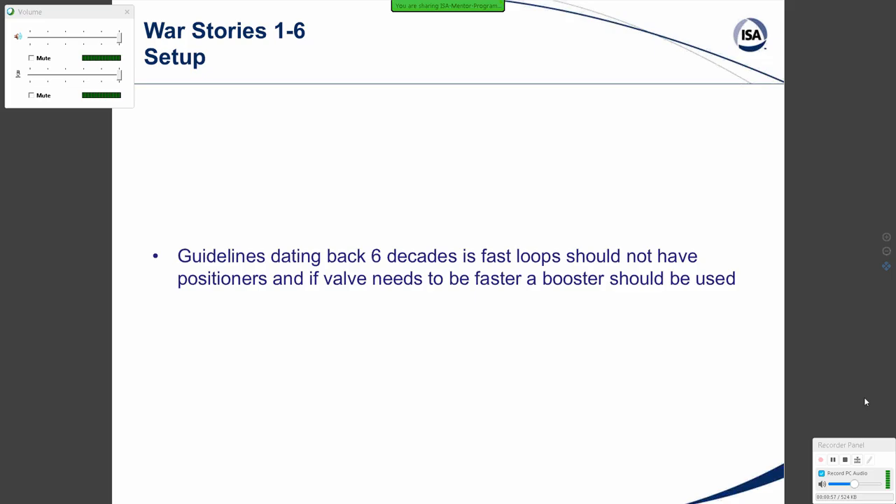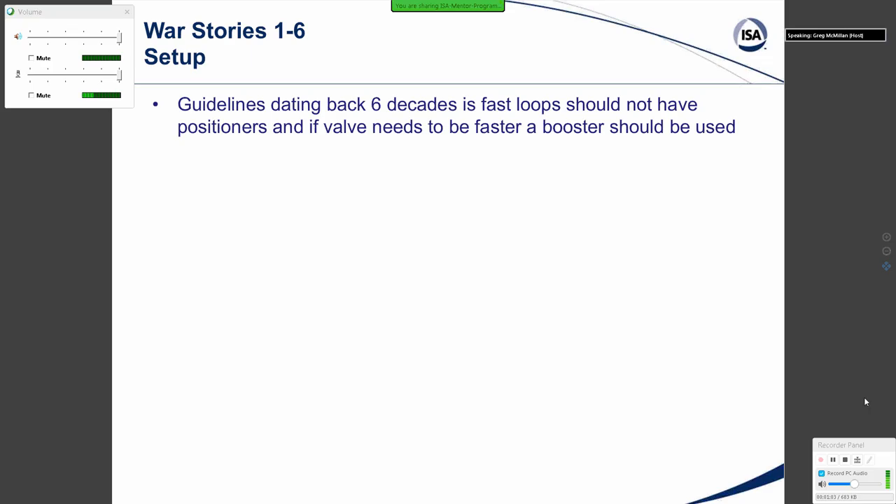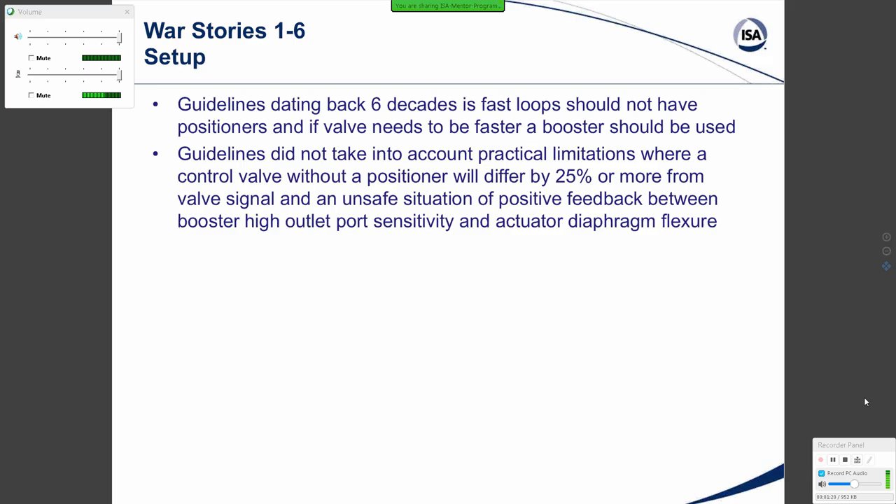Let's start with the setup for War Stories 1 through 6. Guidelines dating back six decades basically all say the same thing: the fast loop should not have positioners, and if a valve needs to be faster, a booster should be used — and we still hear that today. However, these guidelines did not take into account practical limitations where a control valve without a positioner will differ by 25% or more from the valve signal, and an unsafe situation of positive feedback between the booster high outlet port sensitivity and an actuator diaphragm flexure can develop from using a booster without a positioner.